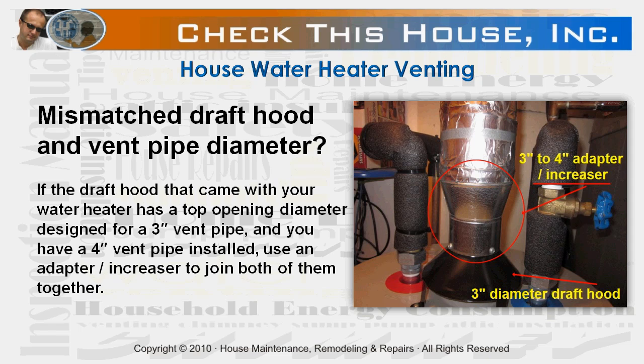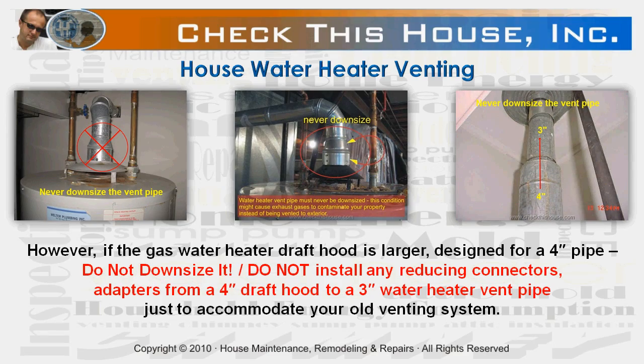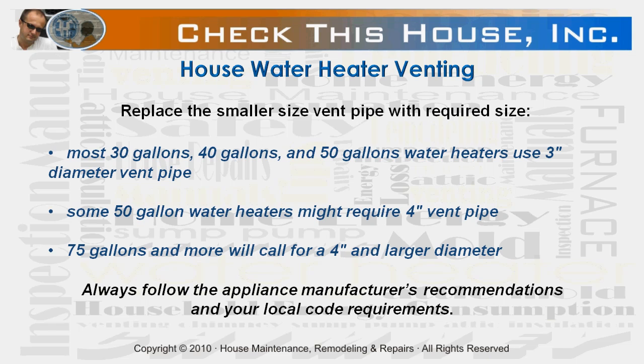When you purchase a new appliance, you might run into a mismatched draft hood and vent pipe diameter. There are two scenarios. For example, if the draft hood that came with your water heater has a top opening diameter designed for a three inch vent pipe and you have a four inch vent pipe installed, use an adapter and increaser to join both of them together. However, if the gas water heater draft hood is larger — designed for a four inch diameter vent pipe — do not downsize it. Do not install any reducing connectors or adapters from a four inch draft hood to a three inch vent pipe just to accommodate your old venting system. Downsizing will prevent exhaust gases from discharging properly through the vent pipe and instead might partially or even completely direct them into your house.